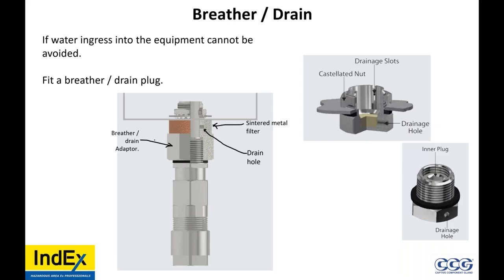Now, what about local control stations? What about fluorescent lights? I could have showed you more pictures. We, in the offshore and onshore industry, find water in things at all times. This little device could be anywhere from $15 to $50, which can save hundreds, if not thousands of dollars by allowing the humidity to bleed off through the breather so that it condenses outside. And if it does condense inside, well, it drains. So a breather drain has 2 functions.